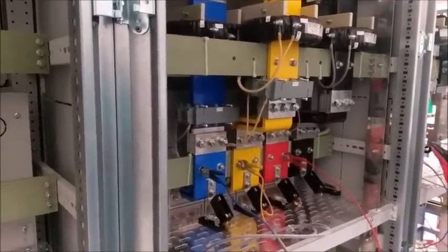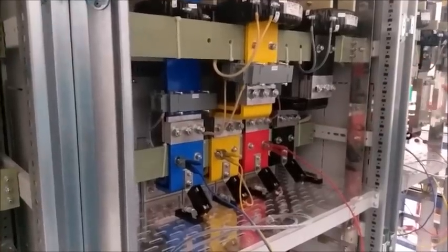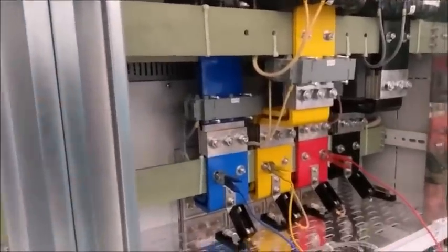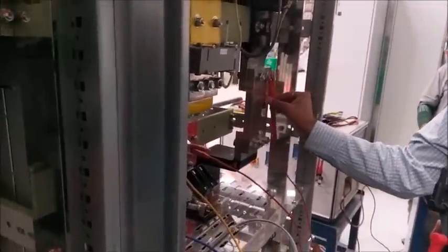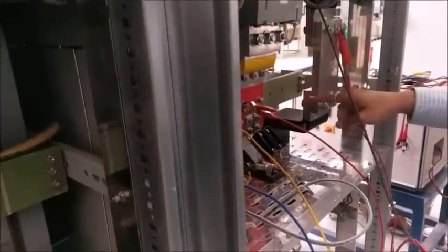Now, suppose I have to test this panel with a Megger test. What I will do is connect this phase to neutral. One phase. This one is neutral, and it is connected here. Or we will check the R phase first. So this is now neutral with R.